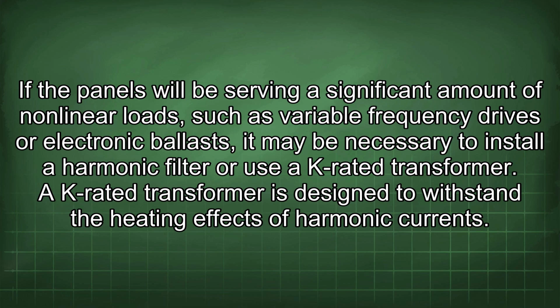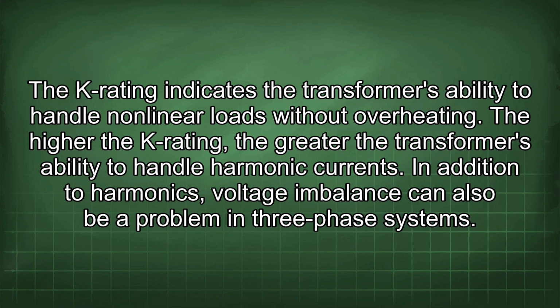A K-rated transformer is designed to withstand the heating effects of harmonic currents. The K rating indicates the transformer's ability to handle nonlinear loads without overheating. The higher the K rating, the greater the transformer's ability to handle harmonic currents.